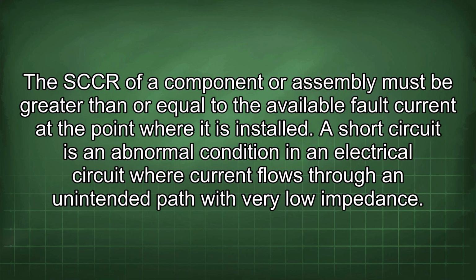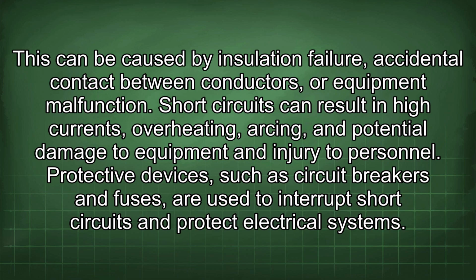A short circuit is an abnormal condition in an electrical circuit where current flows through an unintended path with very low impedance. This can be caused by insulation failure, accidental contact between conductors, or equipment malfunction. Short circuits can result in high currents, overheating, arcing, and potential damage to equipment and injury to personnel.